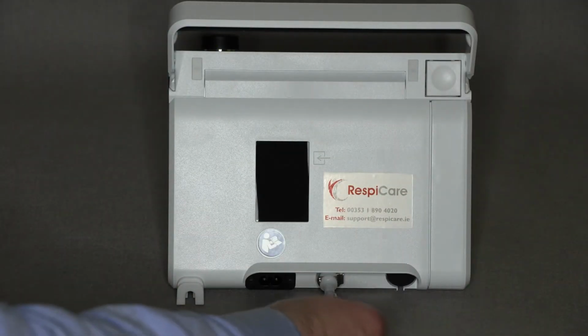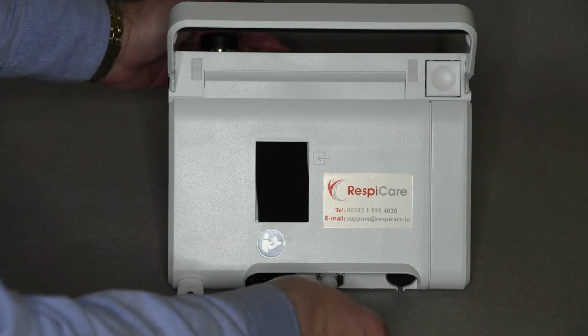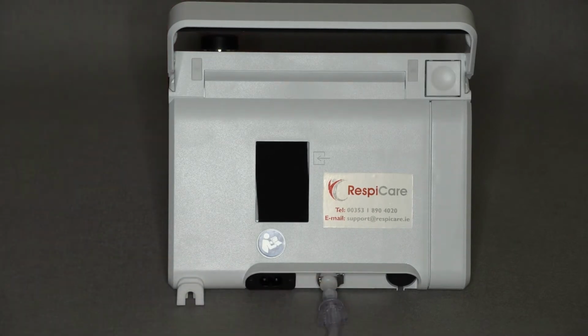When there is a requirement to use oxygen with prismaVENT, an oxygen tube can be attached to this fitting. When the ventilator is turned on and delivering therapy to the patient, any oxygen entrained through this connection will be mixed with the airflow from the device and passed to the patient. When treatment is stopped and the ventilator is turned off, the supply of oxygen to prismaVENT from this connection will cut off as a safety measure, allowing no oxygen through.